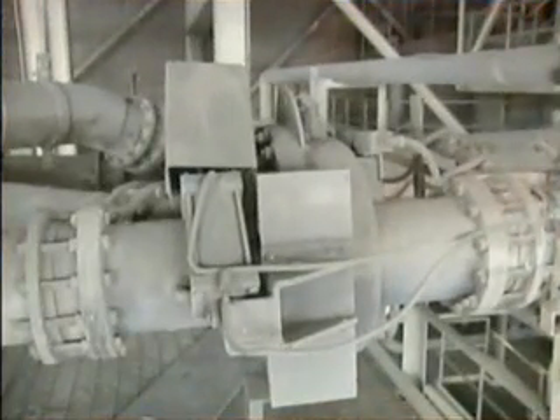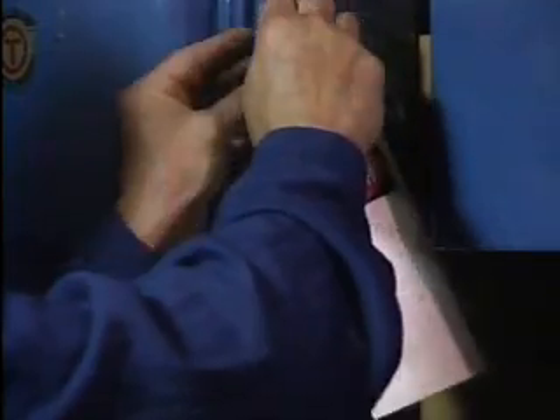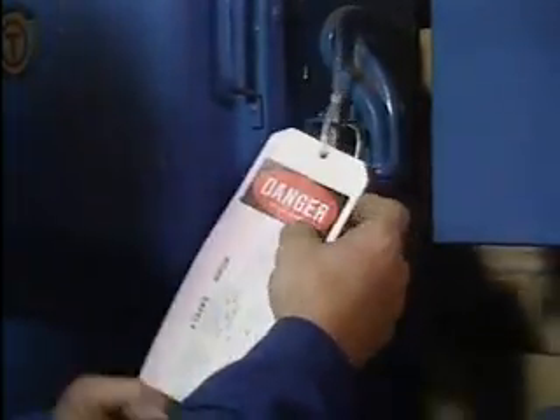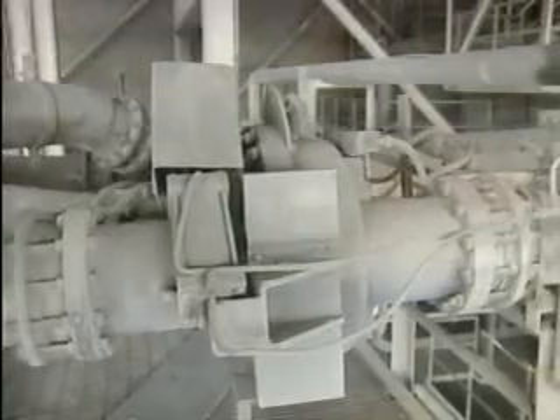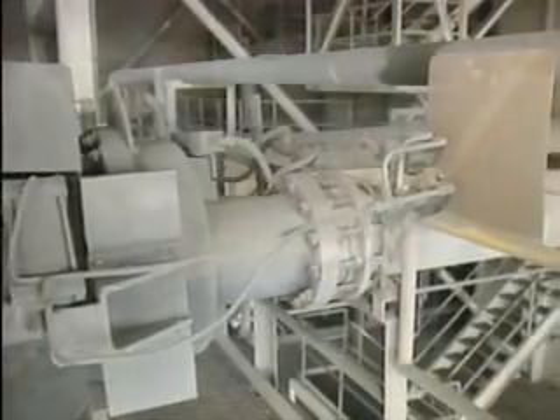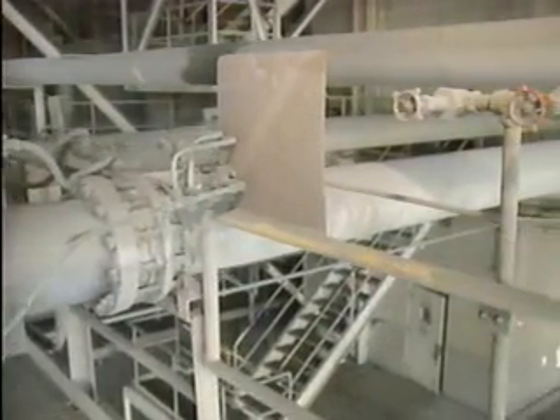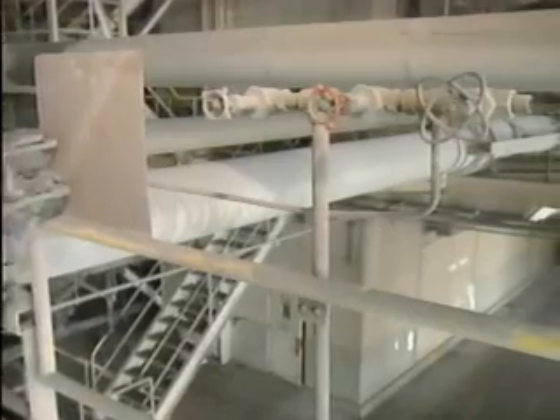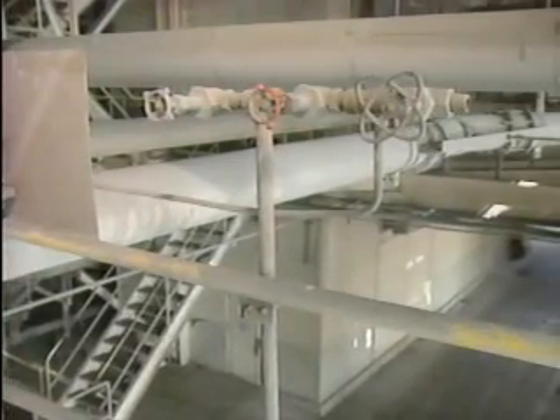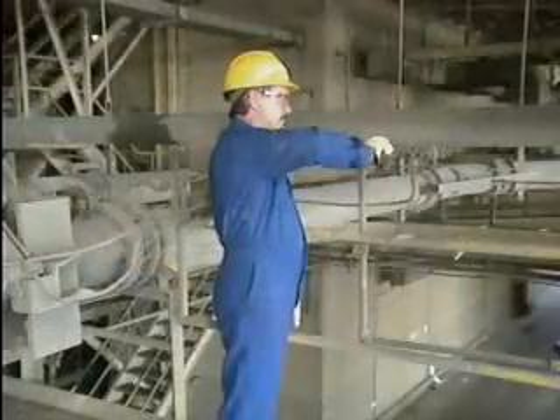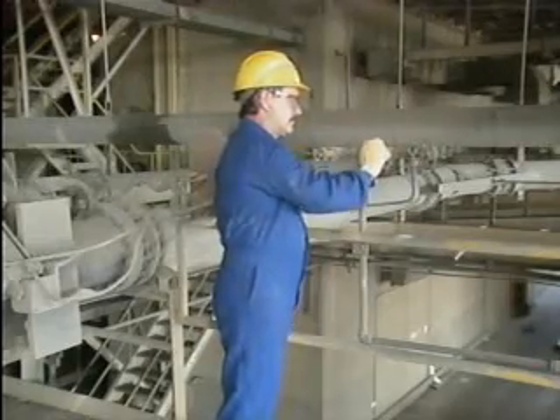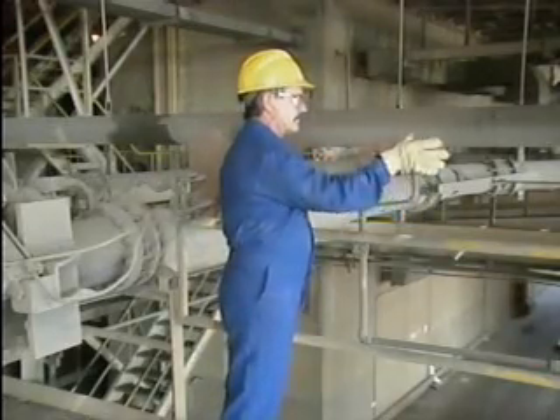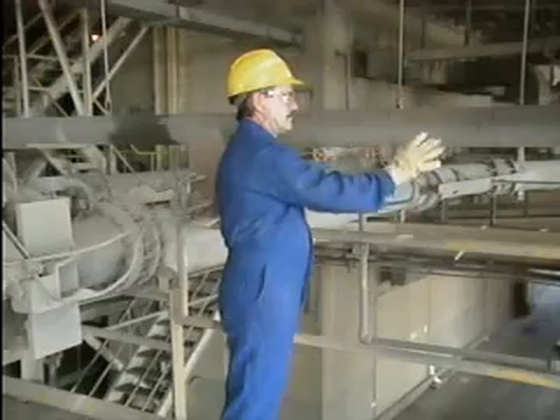This valve operates using air pressure. The circuit has been locked and tagged, so from an electrical perspective, it's safe. However, to be considered safe to work on, all sources of hazardous energy must be removed, and since this is an air-operated valve, that includes air pressure. The electrician turns off the air supply to the valve. Then he opens the bleed valve to release the air pressure in the valve.